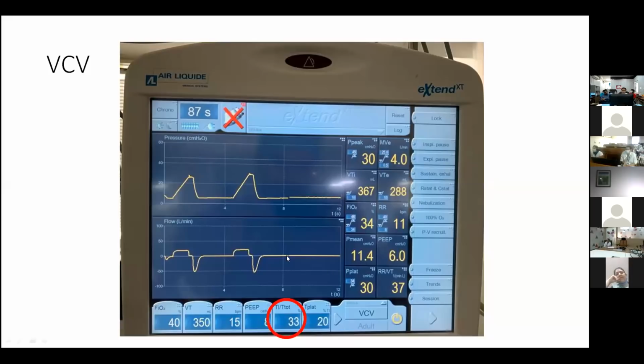Now, if you see these graphics, this is the inspiratory time and this is the expiratory time. We checked our ventilator on a test lung. This is a kind of bag which has very low compliance. If you compare inspiratory time and expiratory time, it is not normal. Normal is 1 for inspiratory and 2 for expiratory. But here the expiratory time is really very less. That means that bag or that lung has very low compliance. So this is how you set your inspiratory to expiratory time.